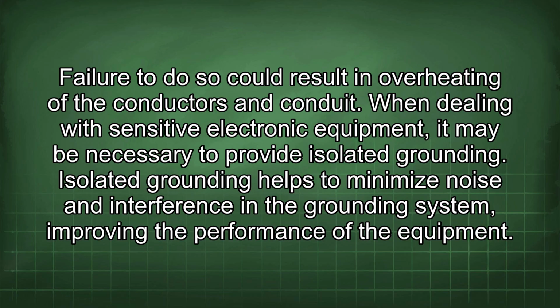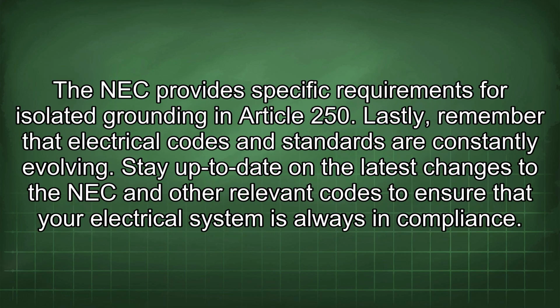When dealing with sensitive electronic equipment, it may be necessary to provide isolated grounding. Isolated grounding helps to minimize noise and interference in the grounding system, improving the performance of the equipment. The NEC provides specific requirements for isolated grounding in Article 250.